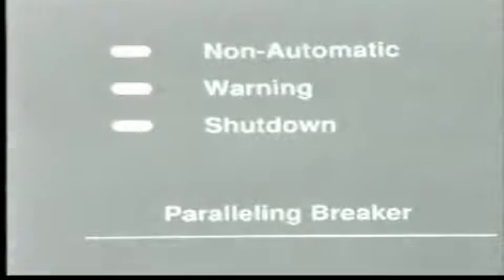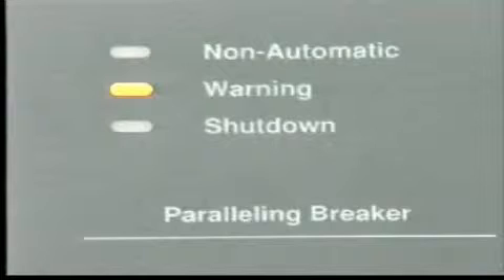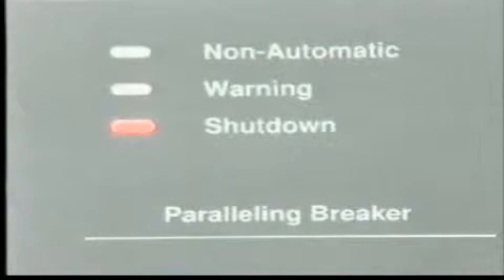When you're working with a generator set and serving a load, there are three conditions you need to be aware of at all times. First, if the generator set is in a non-automatic mode, that is, if it was started manually or unable to start from a transfer switch. Next, if there's a fault that may lead to a shutdown, you need to be alerted to it before it's too late. Finally, if the generator set is in a shutdown status, you don't want to have to decipher a load of symbols and messages to see it. You need the indication right now and in plain view. There's no assortment of symbols and supplier-specific codes on the power command control. It's easy to understand. It speaks your language using common power generation terms that everyone knows.